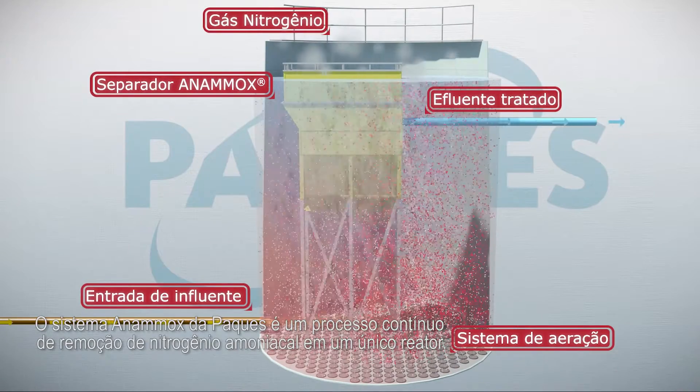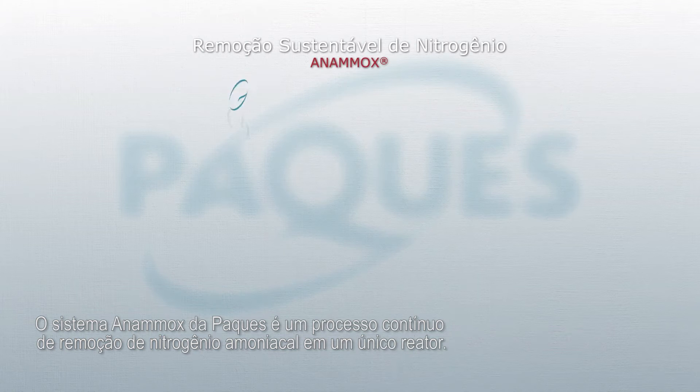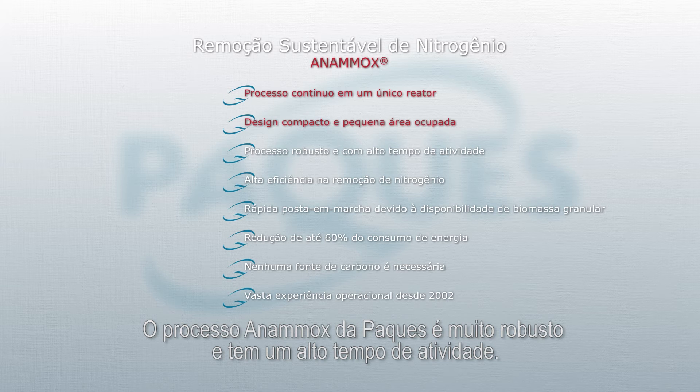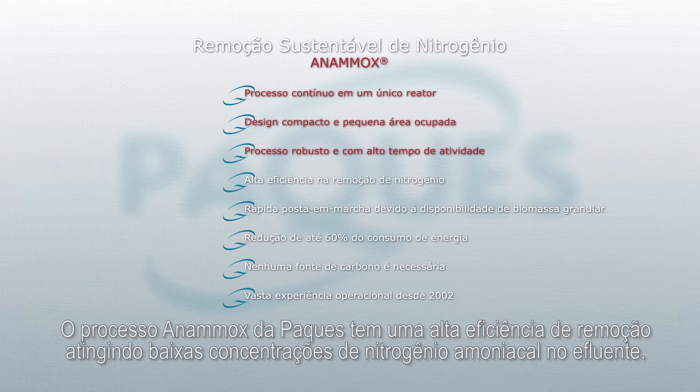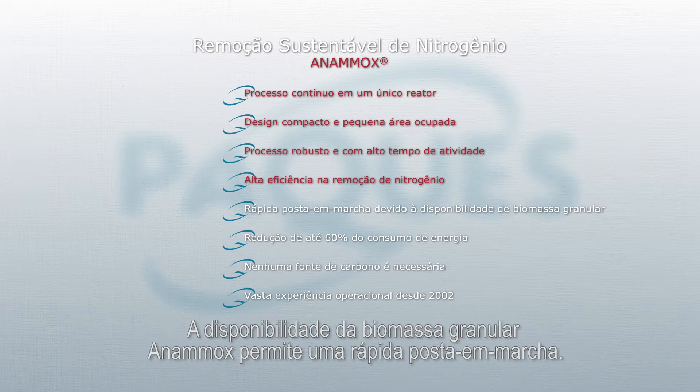The Paques Anammox system is a continuous process removing nitrogen in one single reactor. The use of dense granular biomass allows the Anammox reactors to be compact with a small footprint. The Paques Anammox process is very robust, having a high uptime. The Anammox process has a high removal efficiency, achieving low nitrogen concentrations in the effluent. The availability of granular Anammox biomass allows a quick start-up of the process.